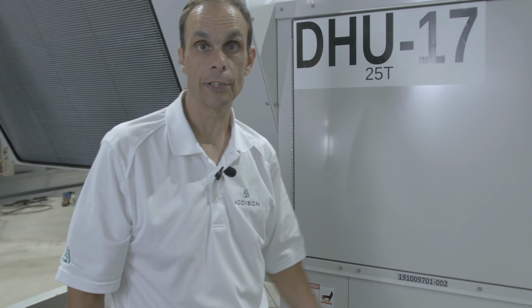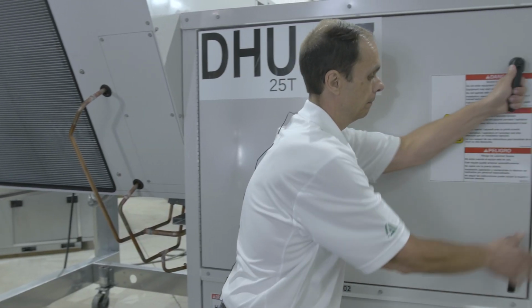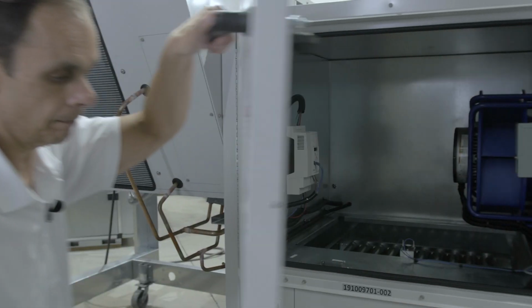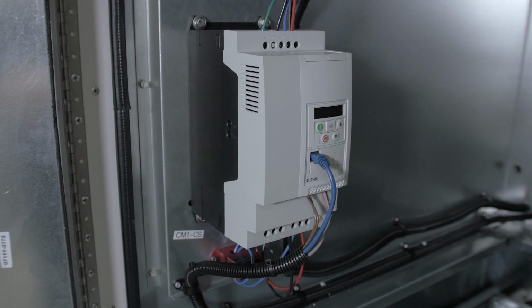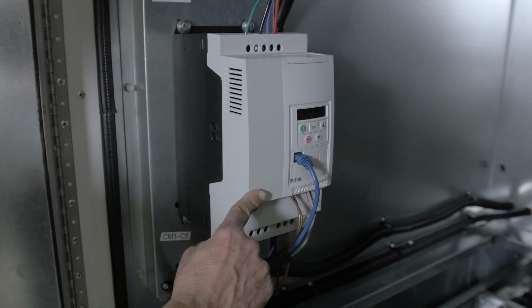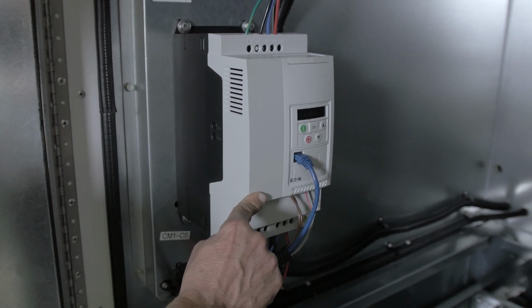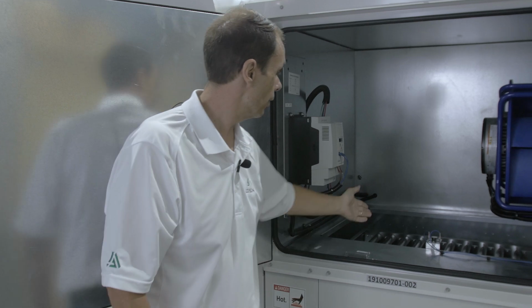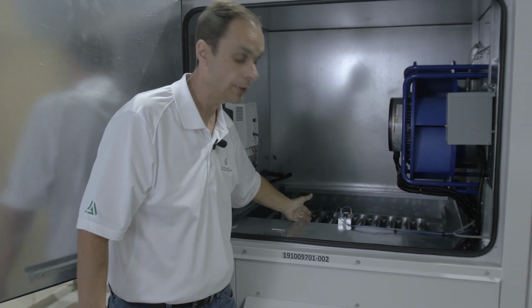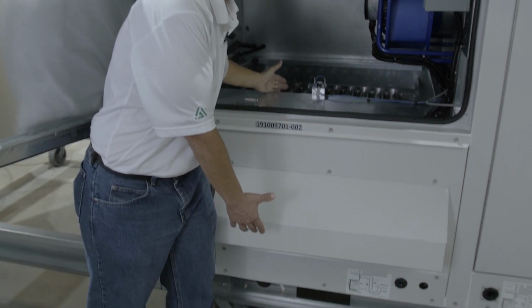Okay, now that we're on the other side of that C4 100% outside air unit, this is your supply fan and your gas furnace here. Let's open up the door and let's see what you have inside. So what you can see inside here now, here is the VFD for the compressor, the variable speed on stage 1. Here's your gas furnace, the heat exchanger tubes here, and all the controls are down below.